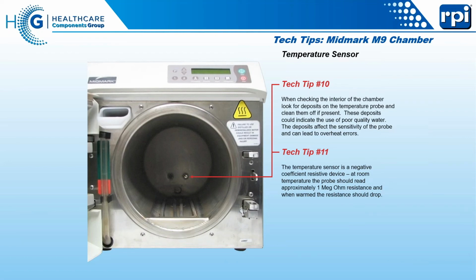You can measure that. In the older machines, the -001 through 19, this is completely wrong. It only applies to the 20 and above. In the 1 through 19s, it's an integrated circuit. You cannot measure it resistively, that gives you any kind of useful information.